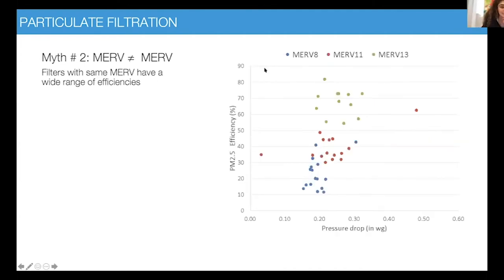The other thing I want to show you, again, each dot here is a unique filter. MERV 13 is in green, MERV 11 is in red, and MERV 8 is in blue. You have efficiency on the y-axis, and on the x-axis you have pressure drop. So the first thing I want to tell you is that not all MERV 13s will have the same efficiency. Similarly, not all MERV 11s, not all MERV 8s. If you want better performance, you take the data from the manufacturer and look at it, and you can have a specification specific to a particulate size. In this way, you make sure that what you're paying for is the highest efficiency and the lowest pressure drop.